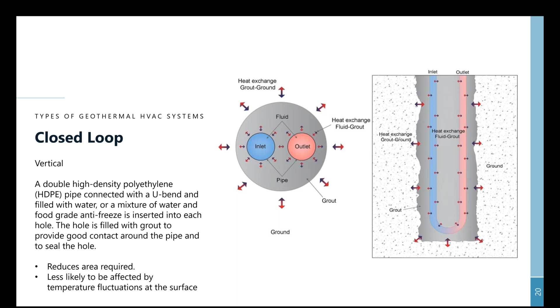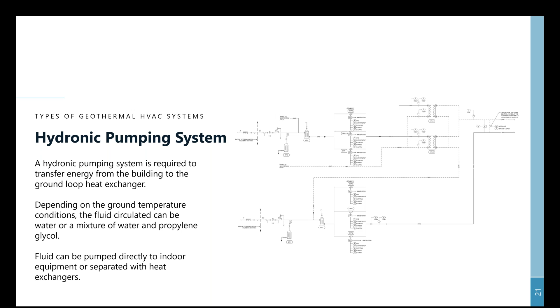Another component of a geothermal HVAC system is the hydronic pumping system. Each of these systems has to have some means of transferring the fluid from the geothermal source into the building for heat exchange. There are a lot of different ways that you can do this. On smaller projects, and even for some larger projects, in a closed loop source you may simply be pumping through the geothermal system and then taking that directly to your indoor HVAC equipment. In other cases, specifically where the geothermal loop requires the use of an antifreeze like propylene glycol, oftentimes we will separate that ground loop from a building loop using heat exchangers. Both applications are perfectly suitable, and you just have to look at the specific requirements and constraints on your project to figure out which hydronic pumping system is most appropriate.